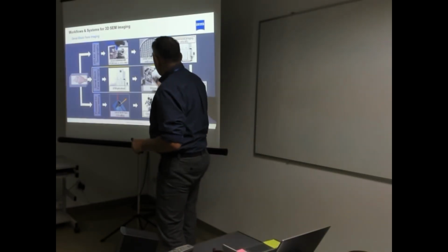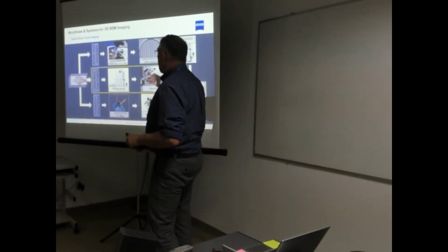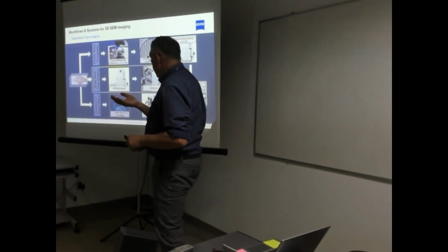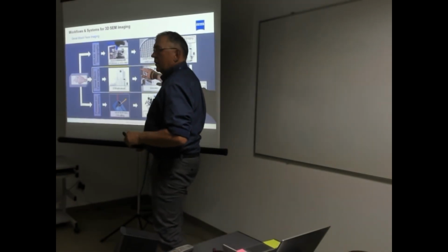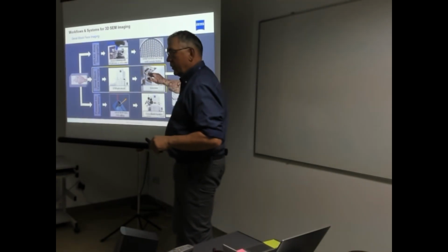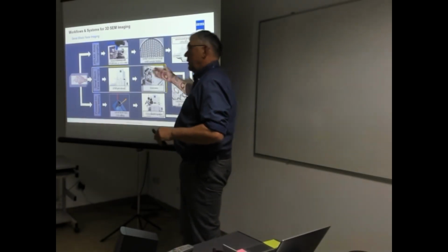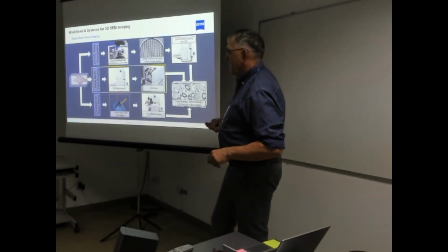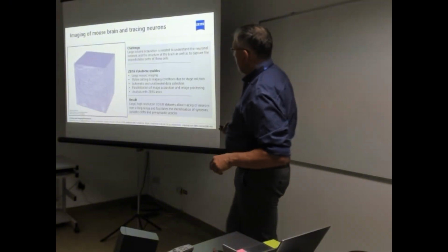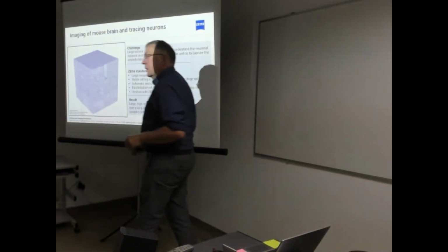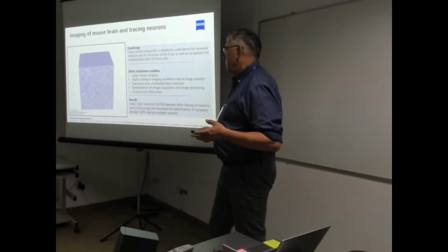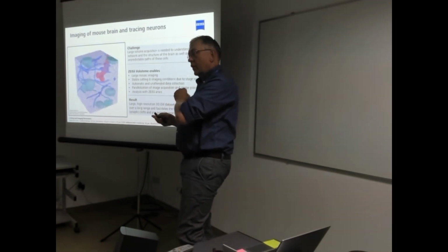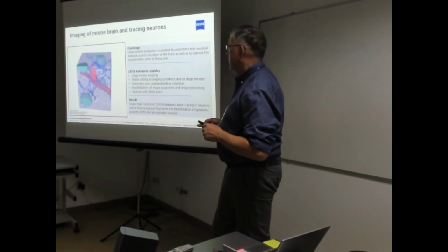What we have here is a door mounting, and the door mounting contains an ultramicrotome. This slices the slice from the top of the sample away, and then the image of the plastic block is registered by the electron microscope, and then the next slice is taken off, the next image is taken. In this way, we can also generate volumes, but in a completely automated manner, and you don't have the hassle to prepare it by yourself, because you only put a block, which has to be pre-prepared, inside the electron microscope.